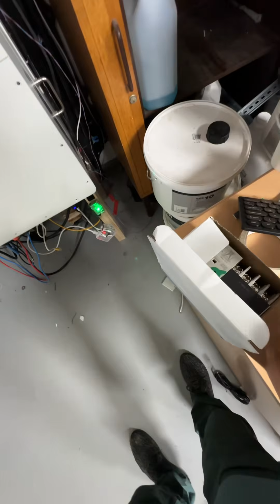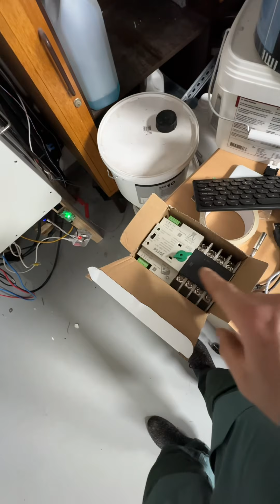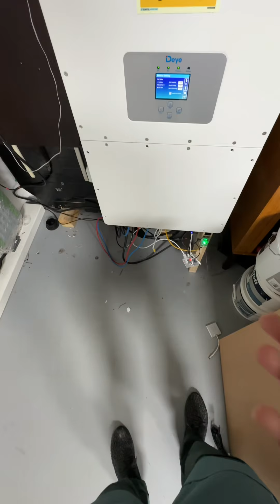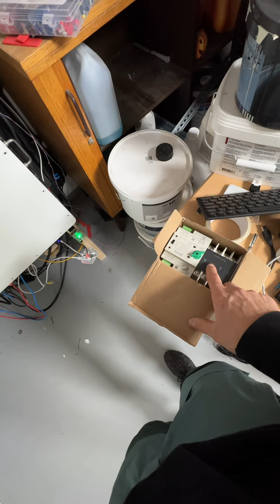I have an ATS here, also a Chinese one, which I'll connect between the grid and the load. That means when the inverter shuts down for any reason, I'd like it to switch back to grid power, because I once did a test, and if for any reason the inverter stops working, I'd lose power in the whole house. So that ATS helps switch over to the grid.